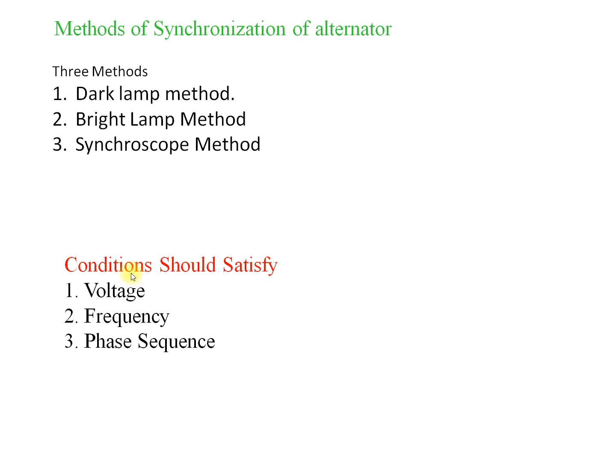In the dark lamp method, here we have a bus bar. This is our main switch. This is the existing alternator from which the bus bar is supplied. To this bus bar we are going to connect our incoming alternator, that is alternator number 2. The incoming voltage will be across this switch. So we need to connect this particular alternator to this bus bar. How to connect this? We will use the first method, the dark lamp method.